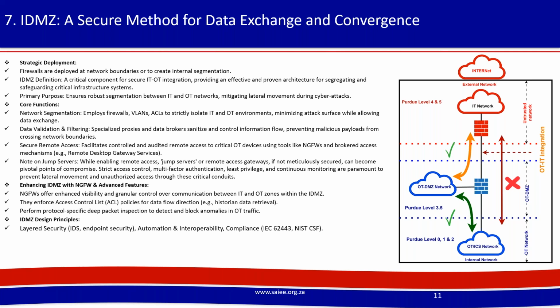It almost sounds like a cliche, what I'm saying, but in reality, some of these jump servers are just left to run to failure. No one checks the logs. Anything can happen there, especially for plants where you've got these mechanical systems. A lot of control system optimization is done there, and sometimes remote access is provided, but you find there's no monitoring being done. So it's very important that the habit needs to change. This must be monitored.